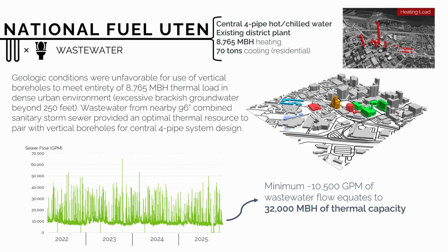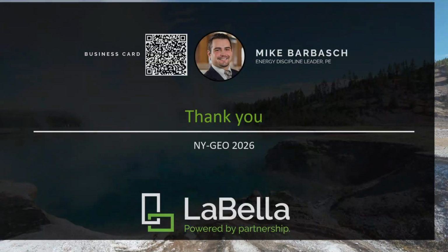We were able to locate a 96-inch combined sanitary and storm sewer main, size some heat exchange, handle the solids, which is a problem unto itself. But aside from that, recover heat from that system. There's 32,000 MBH of thermal capacity in there from a 10,000 GPM average daily flow on the sewer main. You can see that does well exceed the required heating and cooling of the system, but it's going to give the customer some flexibility to expand it in the future, add cooling to some buildings, and increase efficiency. So that's all I have.